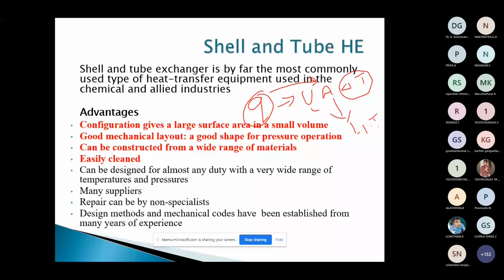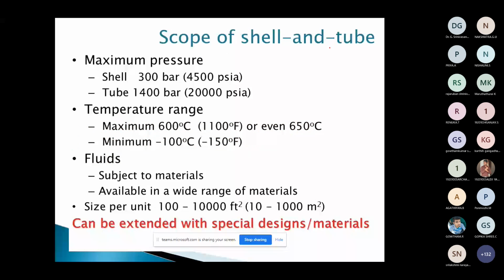You can see the maximum operating pressure in a shell and tube. We have two sides that we will discuss in the next slides. On the shell side, we can operate up to 300 bar, whereas on the tube side, we can go up to 1400 bar. Similarly, for the temperature, we can go to a maximum of 600 degrees in the shell and tube heat exchanger.